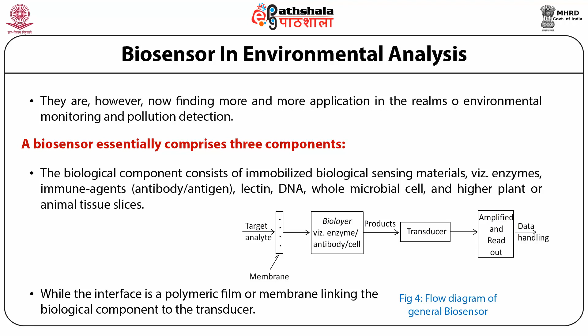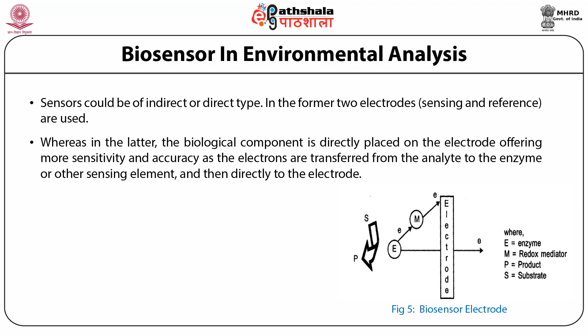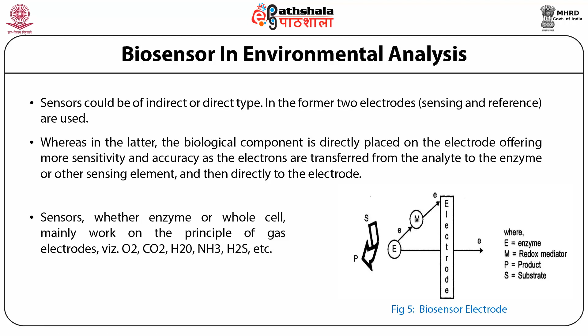This sensor could be of indirect or direct type. In the former, two electrodes are used and it is based upon the principle of amplifying the signal received from the sensor. In these types of sensors, electrons are transferred from the analyte to the enzyme or other sensing elements and then directly to the electrode. After that, the signal is amplified and measured with the help of a microprocessor. Such types of sensors, whether enzyme or whole cell, have been widely used for the measurement of oxygen, carbon dioxide, water, hydrogen peroxide, glucose, ammonia, and hydrogen sulfide gas, as they are based on the principle of gas electrodes.